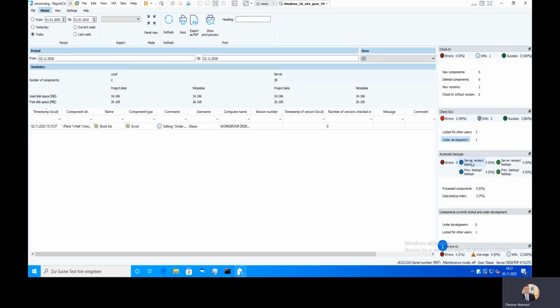And if there are differences, then you can see exactly what is different there, so that you can act and take care that in the PLC is only running code which is stored on the versiondog server. If a supplier changed something and you are aware of it and you see, oh, the change is okay, then you could also say, let's create out of the backup a version and approve it. Then it's again equal between server and device. But if it's not okay, let's say like in a cyber attack and you got per short message an alarm at that moment, let's say a network switch shows open ports which shouldn't be, then you're alarmed, then you should act, because before the cyber attack reaches the PLC, you can already act and get control of the situation.